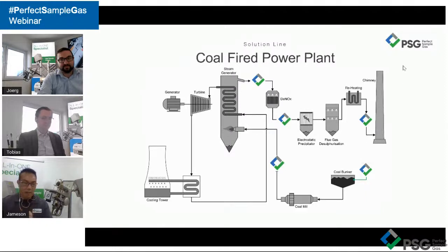Let's put it that in the past, many times we measured NOx at only one point, just to have the reading. But today, the environment has changed drastically: every DeNOx goes into control. Therefore, the response time and the accuracy are so critical, to avoid ammonia slip, any ammonia slip going downstream that may affect the downstream processes, right? Therefore, it is pretty important that I like to share from here. Let's go to the next slide.